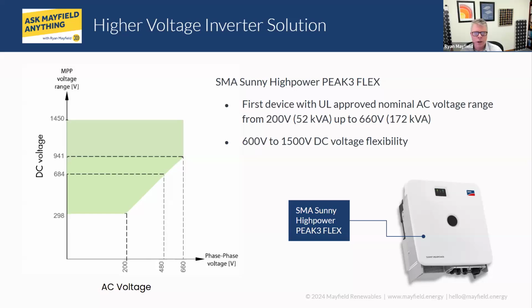Got it. I do want to tie this in with a few questions that I saw in the Q&A. For example, there's one talking about replacing the transformers and when it's a good moment to add a step up or a step down transformer. And I would say that this is something that we look into for every system out there. For example, there are systems out there that are 690 volts AC, where we are close to that range, but we are not there. On the DC side, the array is either 600 volts or 1,000 volts. So there were 690 volts AC systems with 1,000 volts DC arrays.